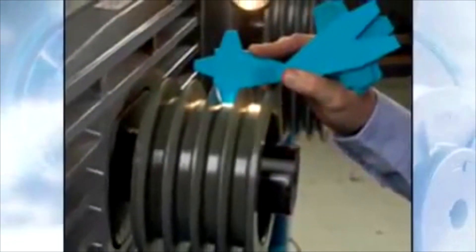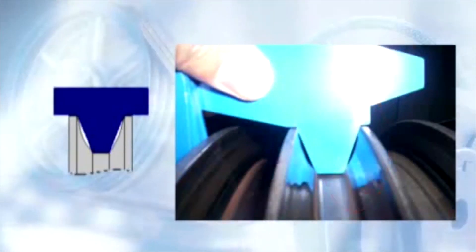Look into the sheave groove with a light source behind the groove gauge. If a gap of 1/32nd of an inch or larger is present, you are losing 5 to 8% efficiency and belt life is reduced. The sheave should be replaced.